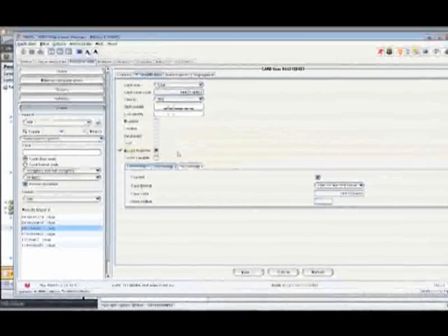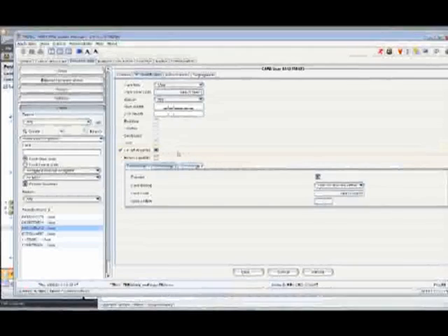Escort required, escort capable. If a card has the escort required property, it means that at gates where the escort control is performed, with this card you cannot enter alone, but you also need the successive reading or the previous reading, this is another property of the gate, of another card which has the property of being escort capable.